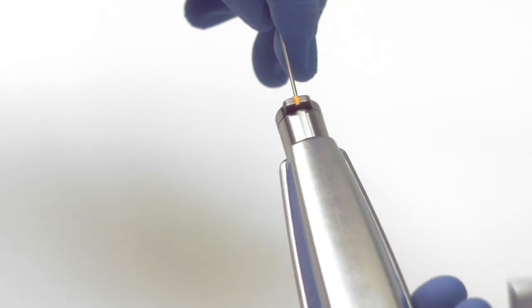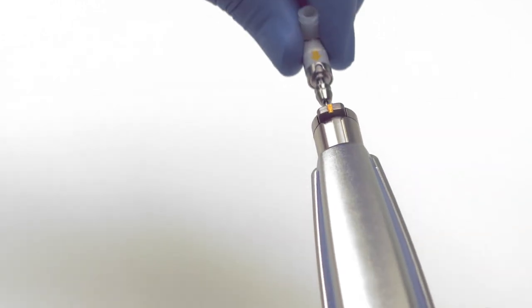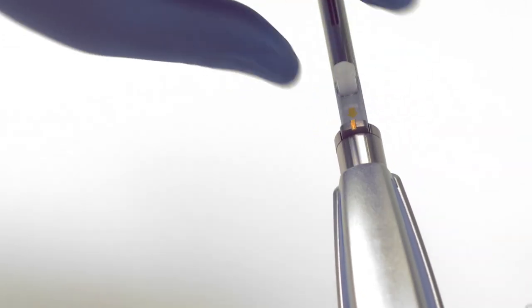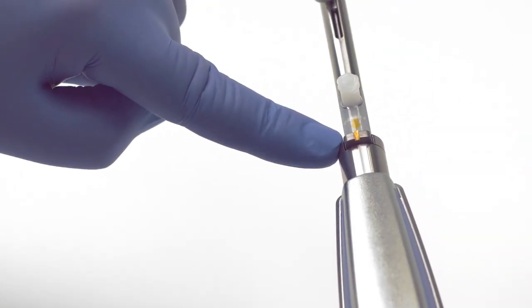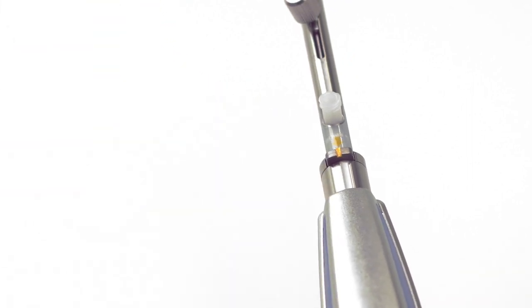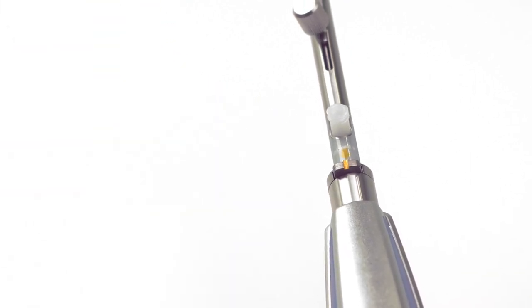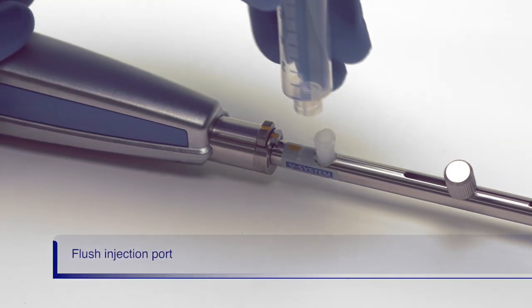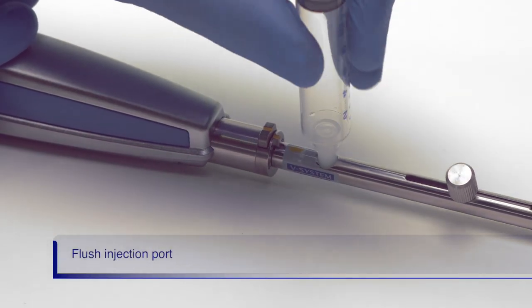Next, we need to align the yellow arrow on the end of the basket to the yellow marks on the handle. Push the basket end into the handle until you feel or hear a click. Flush the injection port prior to passing the basket into the scope.